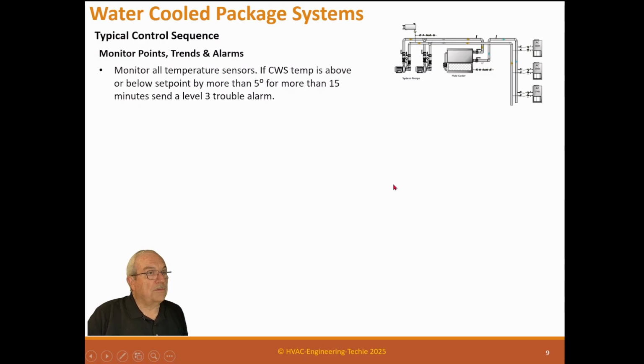Monitor points and alarms. Monitor all temperature sensors. If the condenser water supply temperature is above or below a set point by more than 5 degrees for more than 15 minutes, send a level 3 trouble alarm. Now, level 3 is a trouble alarm that an operator says, okay, I got a problem. I need to look at that when I get a chance.